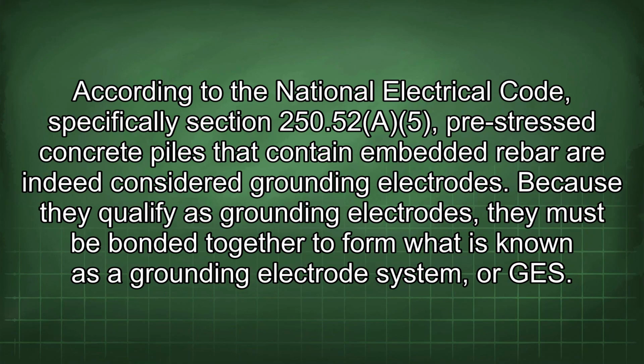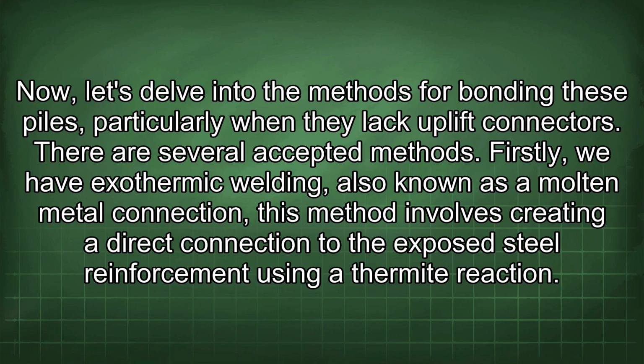According to the National Electrical Code, specifically Section 250.52(A)(5), pre-stressed concrete piles that contain embedded rebar are indeed considered grounding electrodes. Because they qualify as grounding electrodes, they must be bonded together to form what is known as a grounding electrode system, or GES. Now let's delve into the methods for bonding these piles, particularly when they lack uplift connectors.